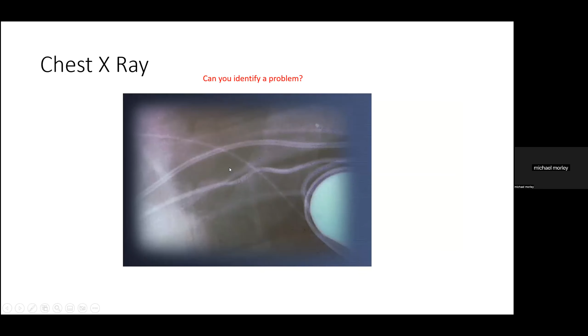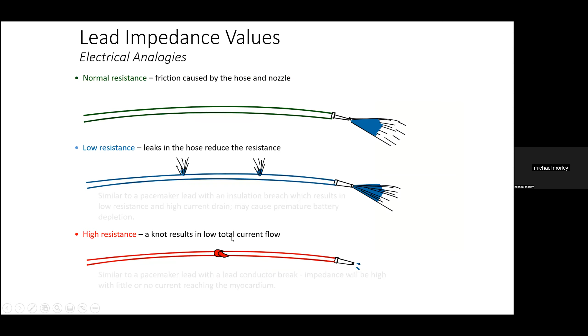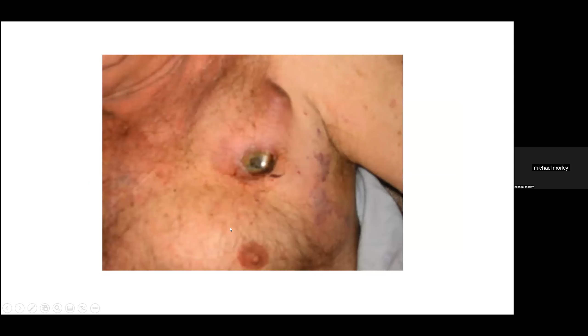And so the other thing that we always measure when we check pacemaker systems is the resistance or impedance of the leads. If the impedance is low, then it suggests that there is an insulation break, and if the impedance is high, then that suggests that there may be a fracture. And this is an example of a pacemaker which has eroded and needs to be extracted.